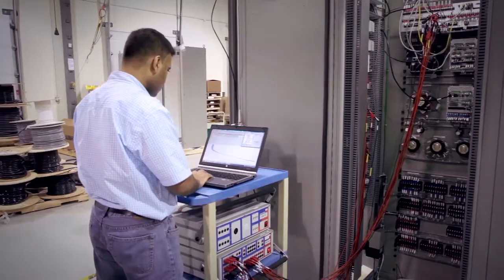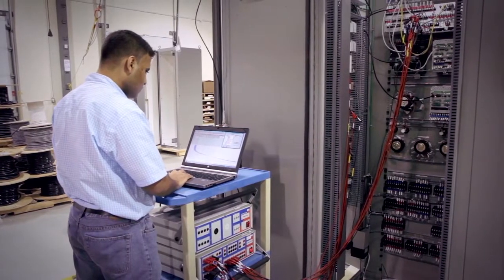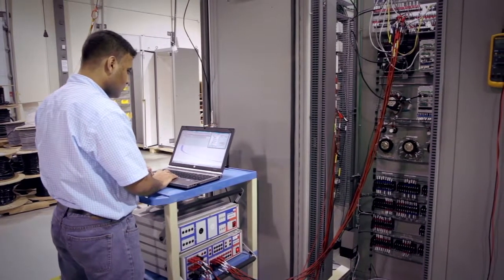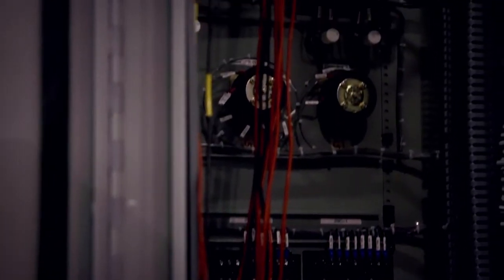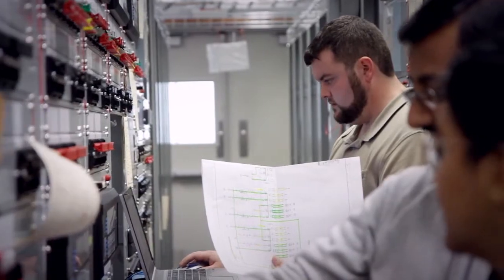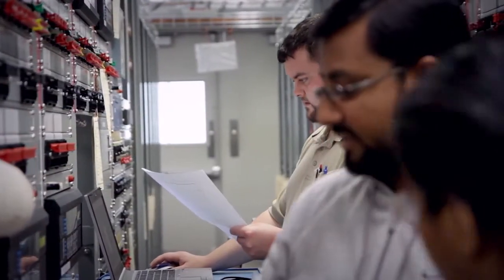Virelec uses the Omicron test equipment for injection testing on relays and other IEDs. Simulated field quantities of both current and voltage are injected into the relays and IEDs at devices called test switches. Injected quantities are compared against values measured by the component device under test, and results are documented on test sheets.